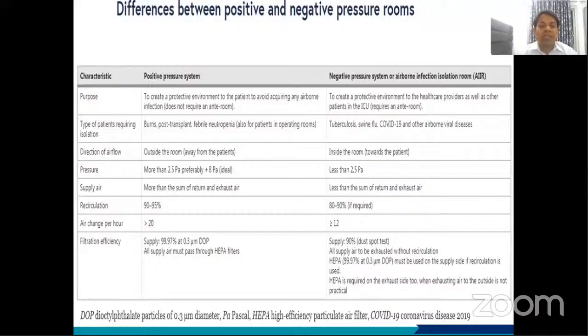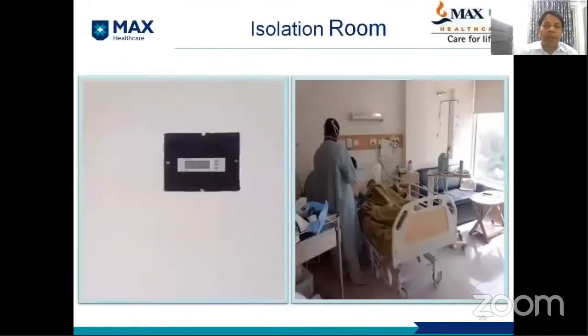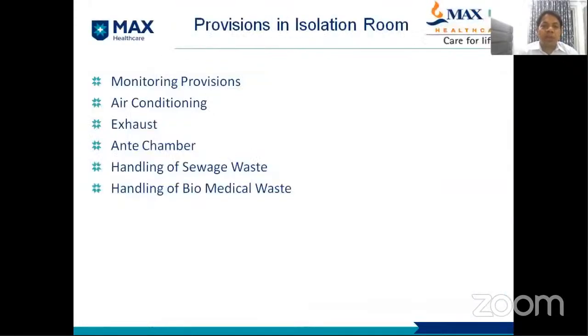Filtration efficacy: supply 99.97% at 0.3 microns by the DOP test. All supply air must pass through the HEPA filters. Whereas in negative rooms, supply is 90% by dust spot test. All supply air is to be exhausted without recirculation. HEPA 99.97% must be used on the supply side if recirculation is used. HEPA is required on the exhaust side too when exhausting the air to the outside is not practical. These are the isolation rooms and the readings.